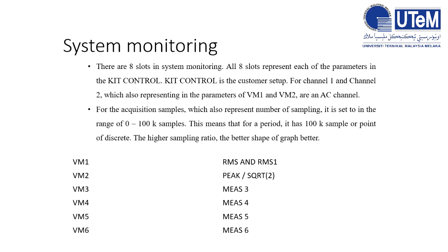Okay, the acquisition sample, which also represents the number of samples, is set in the range of 0 to 100k samples. This means that for a period, it has 100k samples or points or discrete values. The higher the sampling ratio, the better the shape of the graph. In the table below you can see VM1 RMS and RMS1, VM2 peak and square root 2, then VM3 measure 3, VM4 measure 4, VM5 measure 5, and VM6 measure 6.